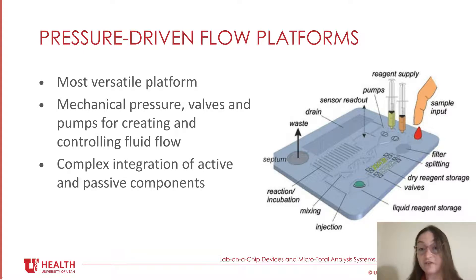A general lab-on-chip device for point-of-care applications contains different passive and active structures arranged so that distinct applications can be carried out on the chip. It contains a means of introducing the sample — here, a syringe where depressing it applies the pressure needed to create fluid flow, though some may have pumps or motors instead. It will often initially go through a filter to clean up the sample and separate plasma from cells. Valves help control the timing and volume of reagent mixing. The cartridge also includes dry and/or liquid reagent storage, a means of mixing, incubation of fluids, and structures for analytical readouts and waste.